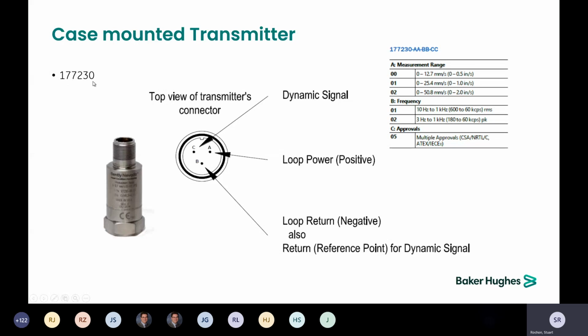The 177-230 gives you inches per second. We offer 3 different scale ranges. Again, it is an active loop power, so you have to supply the voltage. And it does have the dynamic signal: just between the C and B pins will give you the dynamic signal.